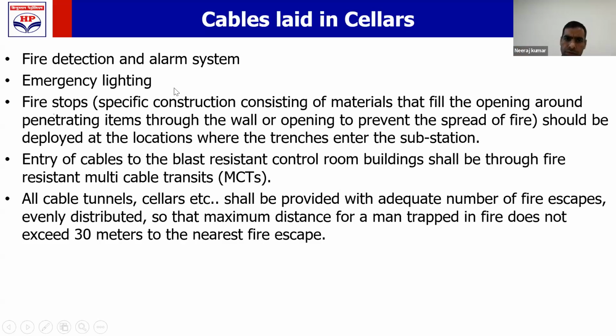What is fire stop? कुछ नहीं है, जहाँ पे आपकी केबल्स सब स्टेशन के अंदर आती है, उस जगह पे you need not keep the opening open. उसको एक fire retardant material से fill कर देना है, so that if there is a fire outside the substation, it does not travel inside, and if there is a fire inside the substation in the cable, it does not travel outside. That is called fire stop. So your substation shall also be provided with the fire stop at the cellar level.